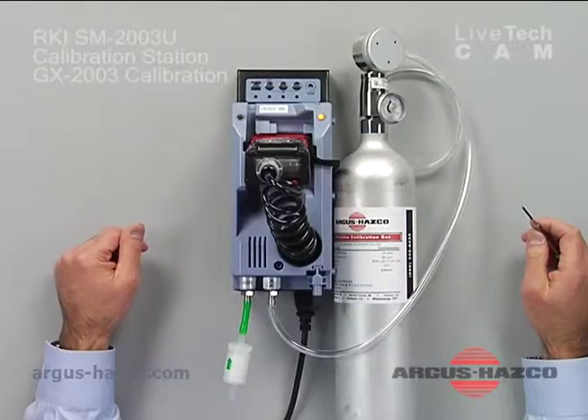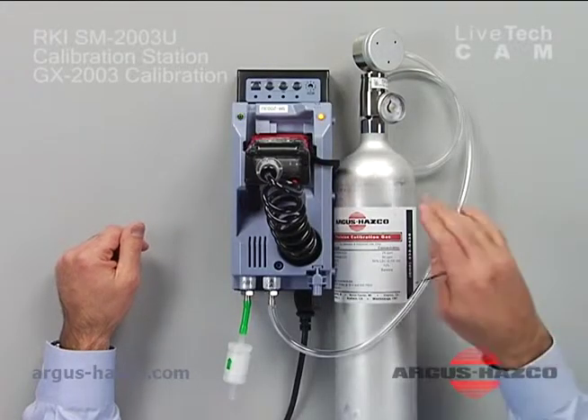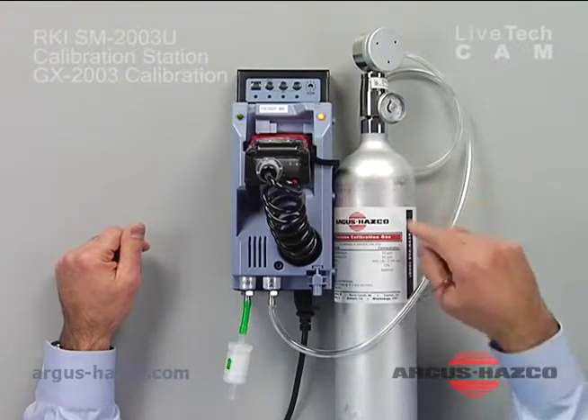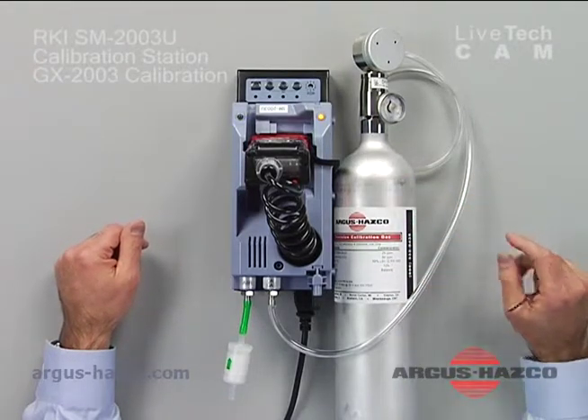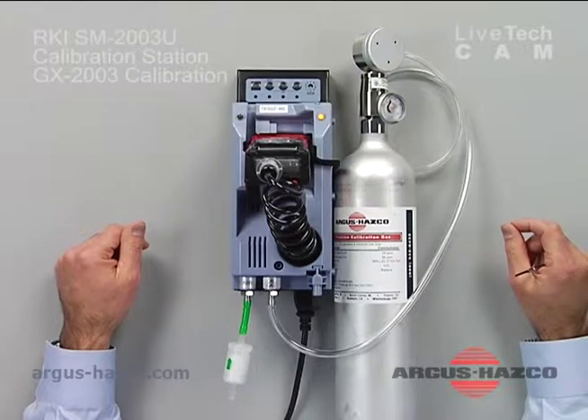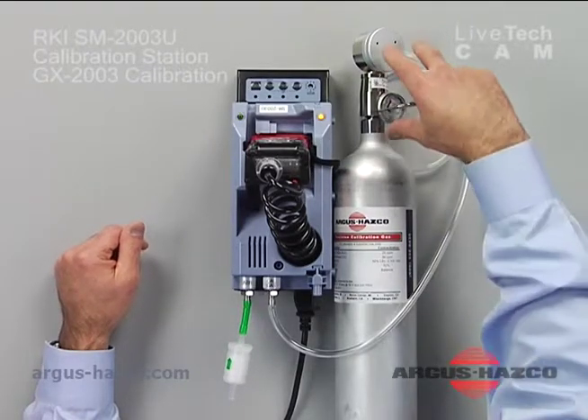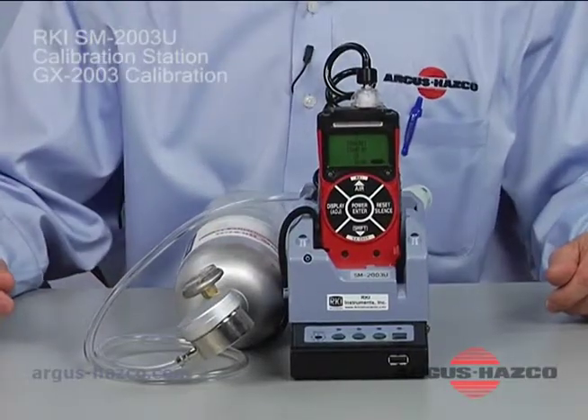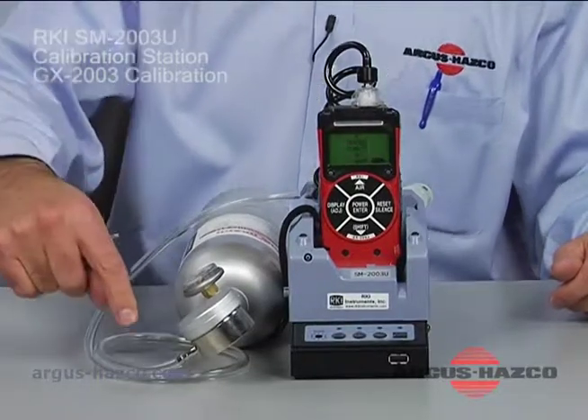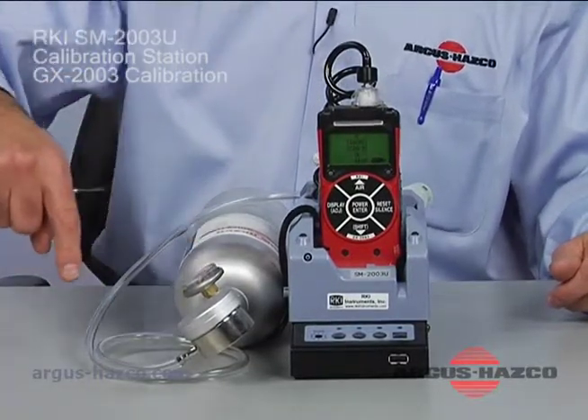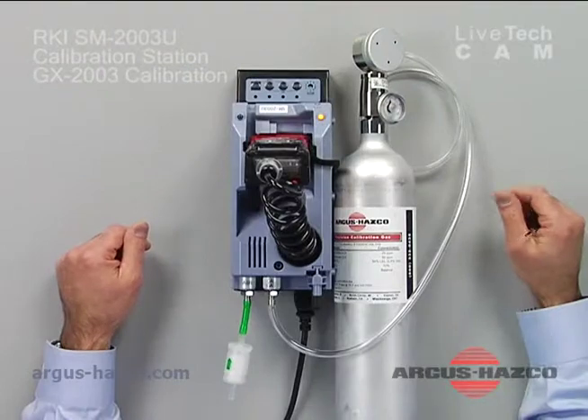Next, we're going to discuss the use of the calibration station. I just want to review how everything ties together with the calibration station and the instrument and the cylinder of gas. We have the cylinder of gas that has the concentration that the unit's been set up to receive on the label. We have the demand flow regulator that's attached to the cylinder. Then a smaller diameter Tygon tubing that is running to the calibration station.